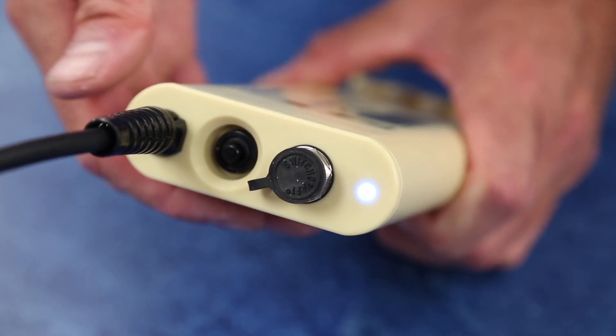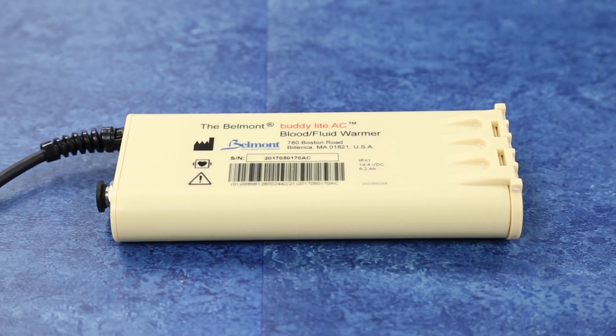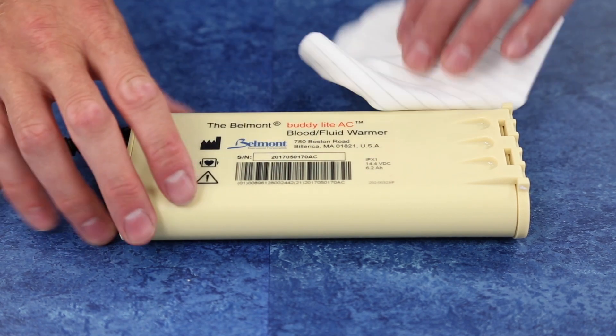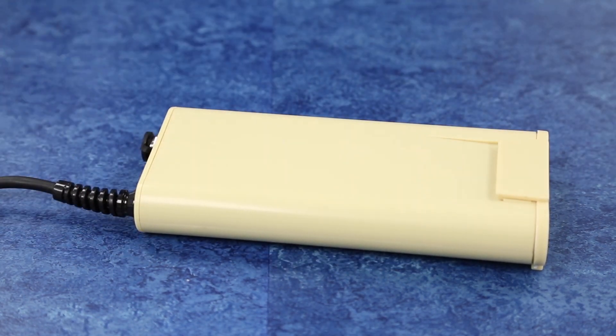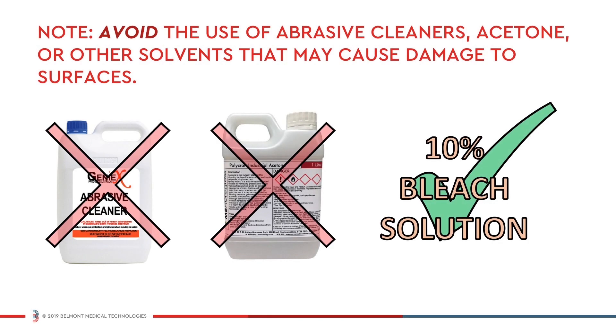To clean or disinfect the system, first power off the device. Using a soft cloth with water or with a 10% bleach solution, wipe down the outside surfaces of the battery housing, the power supply, and the heater unit. Note, avoid the use of abrasive cleaners, acetone, or other solvents that may cause damage to these surfaces.